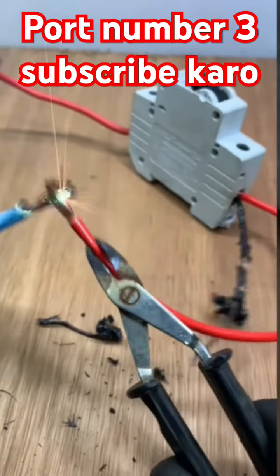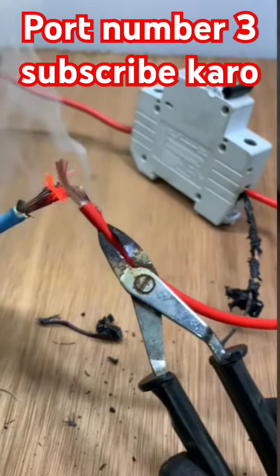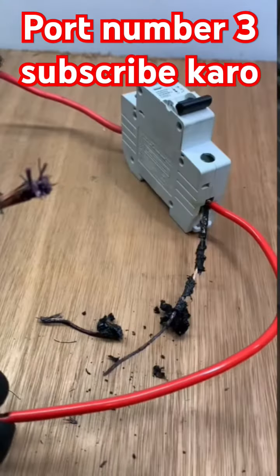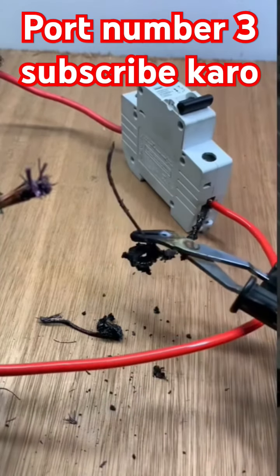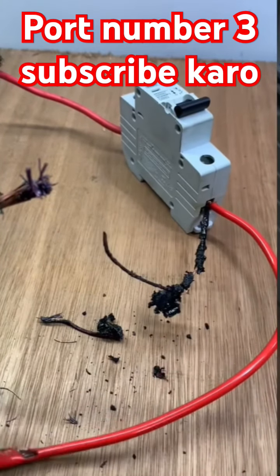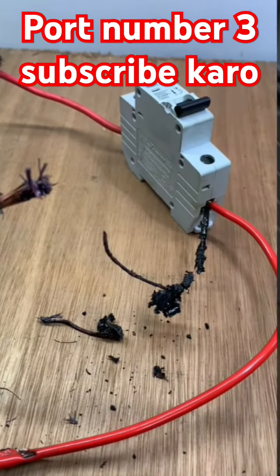Now I'm going to cause an overload with the 6mm wire. Oh, the circuit breaker tripped and the cable remained intact, so it wasn't damaged. Look here, the 1.5mm cable caught fire, but the 6mm is intact.